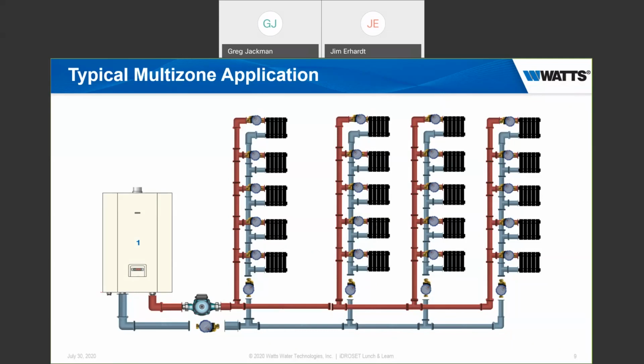And what will happen as we get toward the top, that top radiator, without the benefit of balancing, that radiator will be starved for flow, simply because of the longer pipe run, the greater pressure drop. The water is going to flow through the path of least resistance. So that top radiator gets starved. So as part of the balancing process, really what we're doing is artificially choking down the flow on those lower radiators to push flow up to the upper radiators. It's a simplified way of describing it, but basically what we want to end up with is equal flow, or flow that's appropriate as designed, for each one of those radiators. So the balancing becomes really not only important, but it can also be a time-consuming job, because every time you adjust one balancing valve, it changes the flow in another.